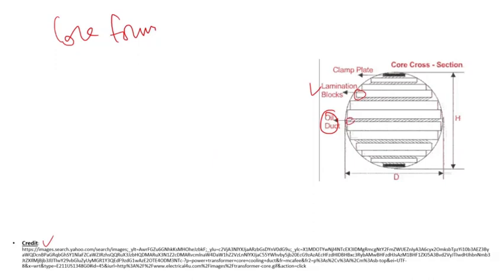So you have oil ducts, and you can create as many as you need to keep the temperature of the core within an acceptable level. You don't want it to get too hot, because next to the core is oil, so it's going to overheat the oil, and there is also paper insulation, press board, wood, and so forth.